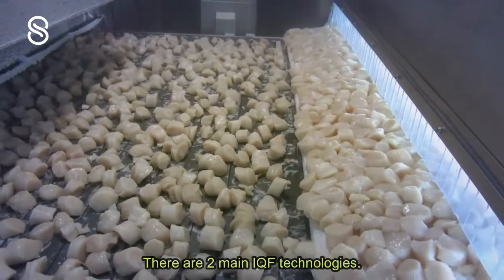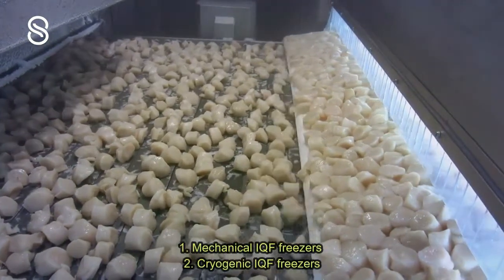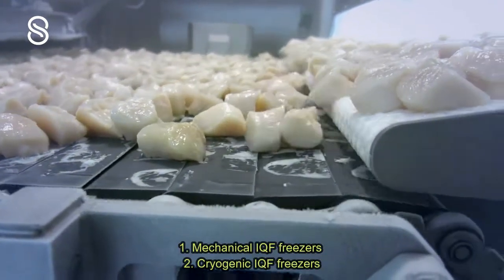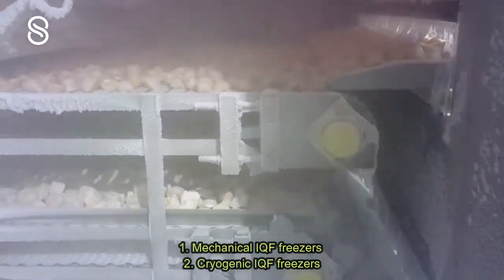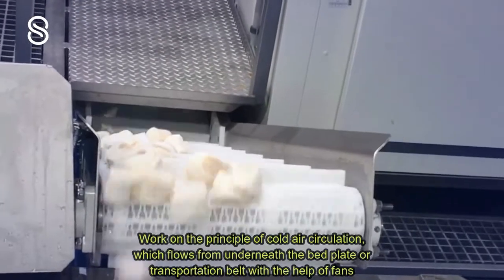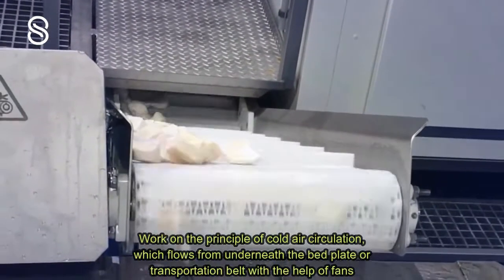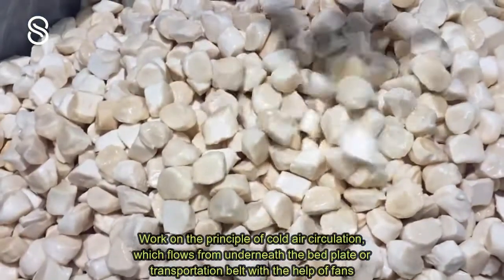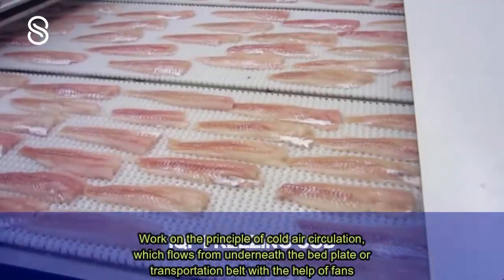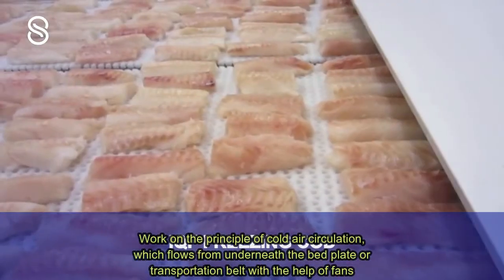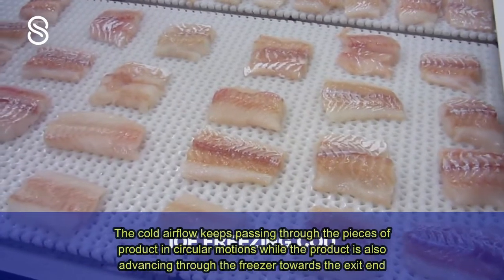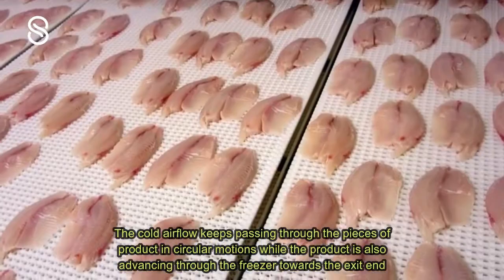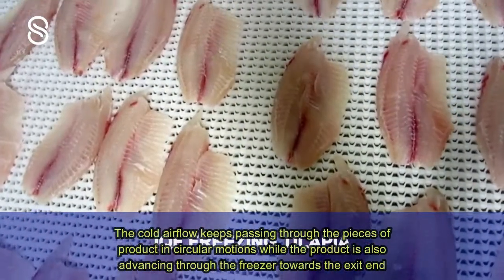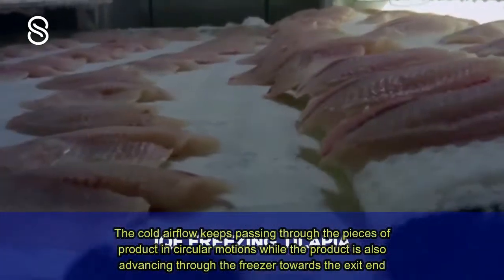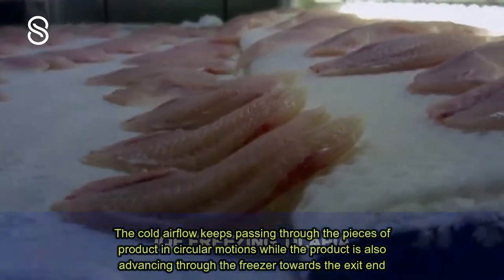There are two main IQF technologies. One is the mechanical IQF freezer and two is the cryogenic IQF freezer. Mechanical IQF freezers work on the principle of cold air circulation, which flows from underneath the bed plate or transportation belt with the help of fans. The cold airflow keeps passing through the pieces of product in circular motions while the product is also advancing through the freezer towards the exit end.